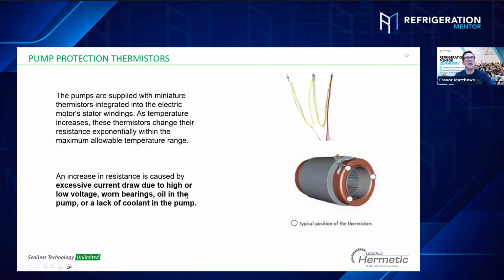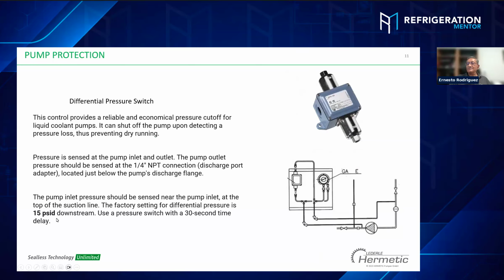Okay, so I do chiller training, and in the chiller training it's on glycol, so not CO2 at this point in this system. But that differential pressure can change if all of a sudden the suction line is too long, or if it overheats and gets smaller, which will drop the suction pressure. Is that what you're talking about, the differential pressure from the suction to the discharge? Basically, when you have low differential pressure, it's because the pump is cavitating. That is the main thing. When the pump is cavitating, the differential pressure across the pump is minimized, and the pump is going to stop before any more damage. That's the whole purpose of this device, that we don't want to damage the pump because the pressure drops off. Yes, exactly. The main thing is to prevent the pump from cavitating, for low pressure and high pressure.